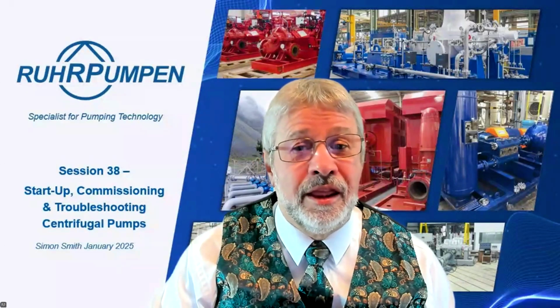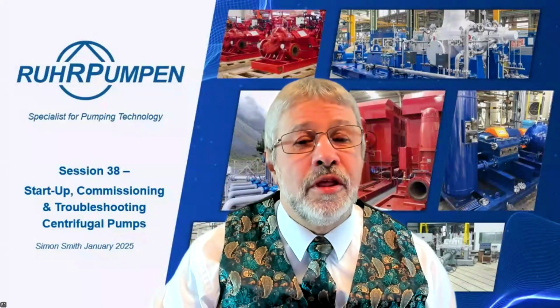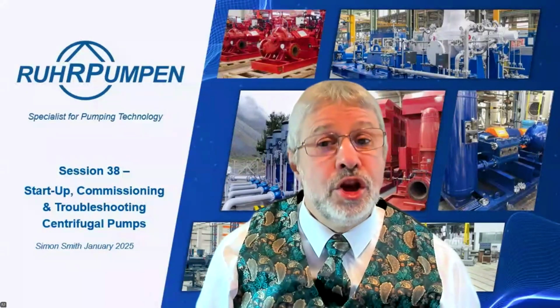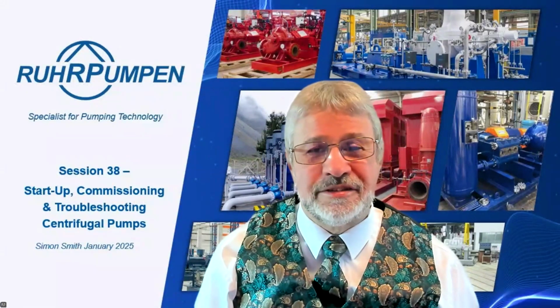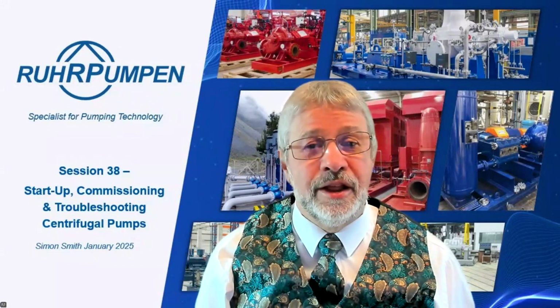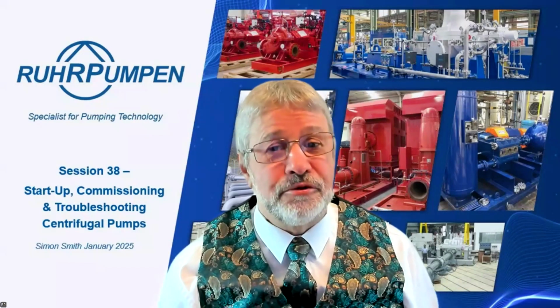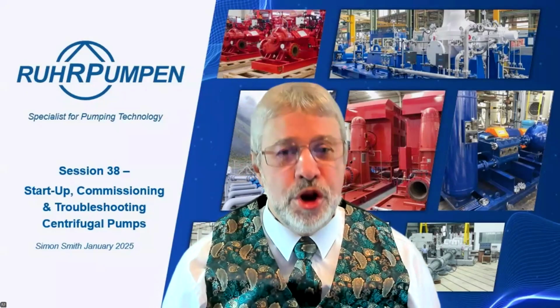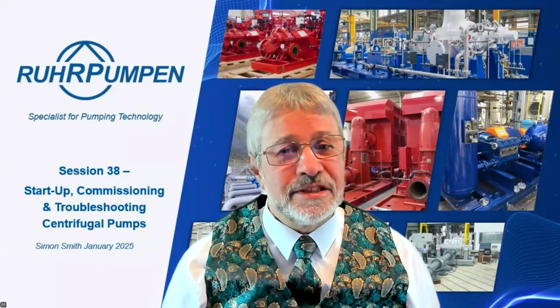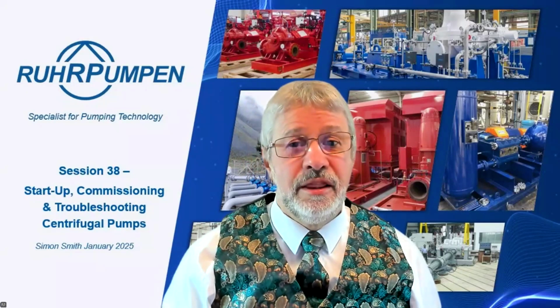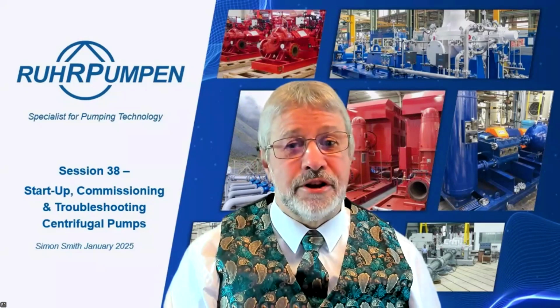Do vertical pumps such as VS4 need to undergo modal analysis if the length of the pump is around 4 meters, including motor? Yes, I think it could well be that about 20% of vertical pumps in new installations that haven't been checked out before will have a critical speed problem, a natural resonant frequency problem. About 20% of new untried installations will have that. And it's usually a fairly simple thing to either stiffen or soften the system to get you away from that natural resonant frequency.